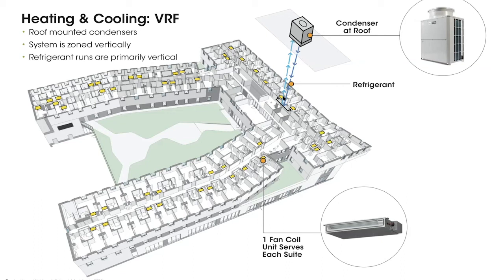Every room has a fan coil unit. In the two-bedroom suite, one fan coil serves both rooms. For a single unit, one fan coil serves one room. A cost analysis done specifically for this job at DD phase compared VRF plumbing costs to four-pipe and two-pipe fan coil systems using two comparable multifamily projects. The VRF plumbing price came in a little lower than the four-pipe and slightly higher than the two-pipe — all relatively the same at 100% DD phase. VRF is not by default more expensive.